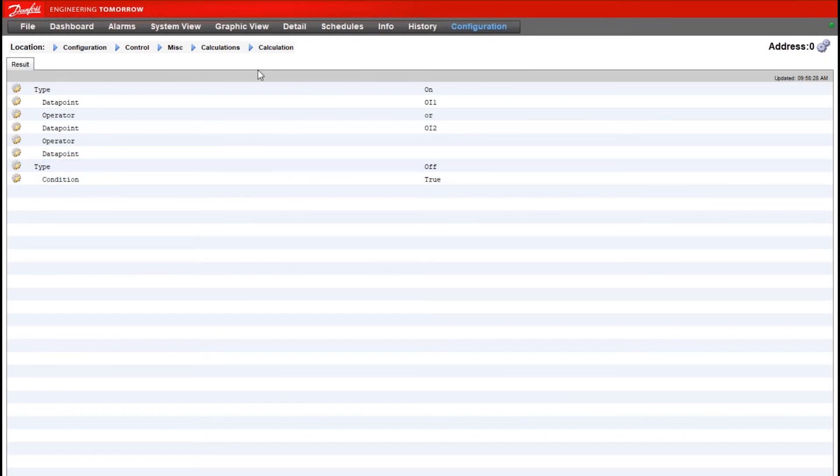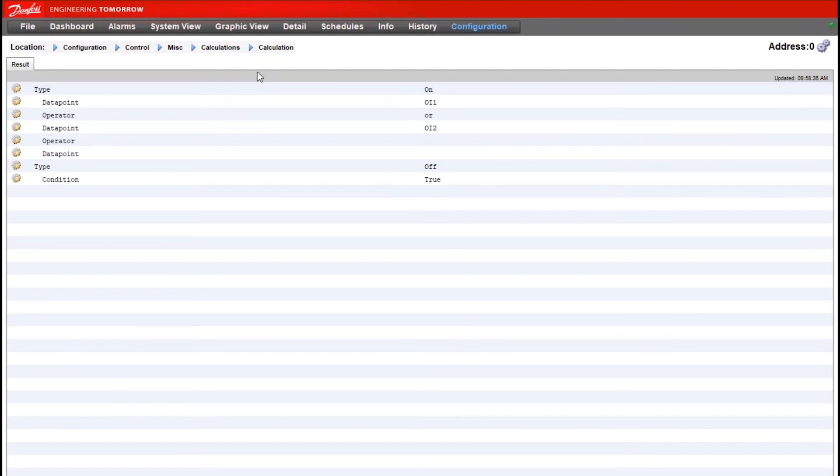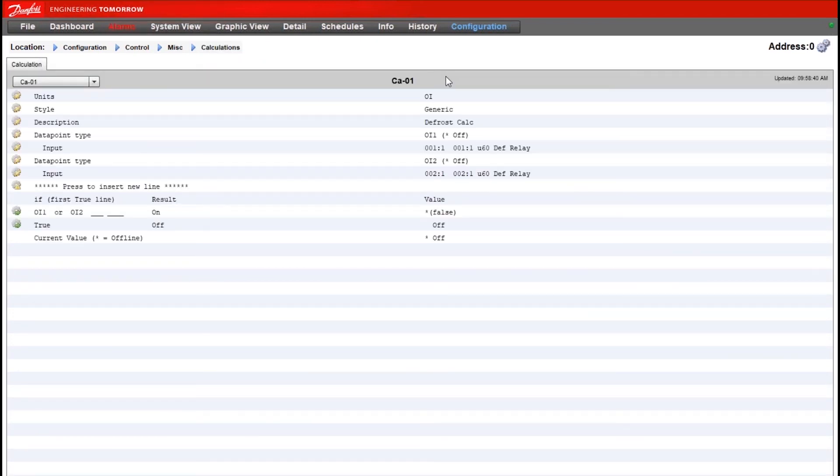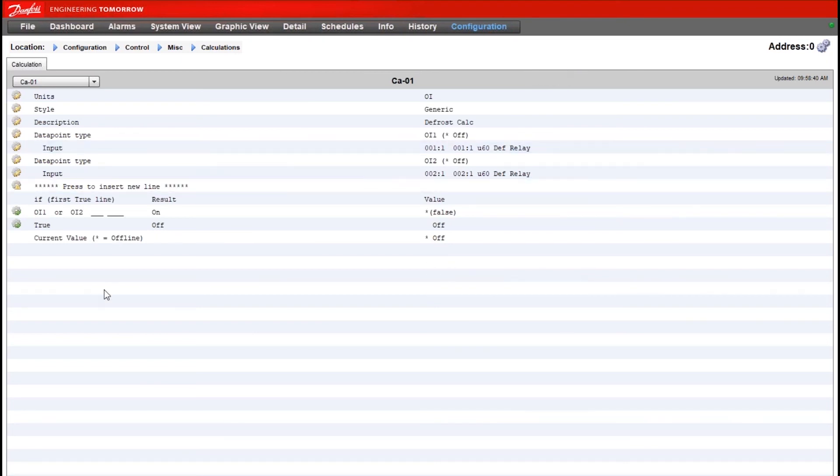So this would be the configuration that would allow us to turn the calculation on any time either of our defrost relays are on and then turn the calculation off if neither of the two are on. Click on the calculations option there to return to the full setup of the calculation so you can see the initial setup and then the results all configured on the same screen.